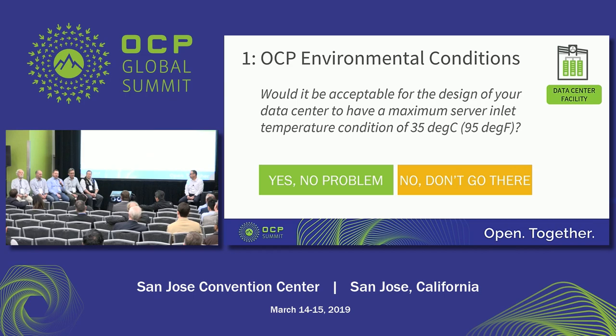I'll skip past the technical bits because I think what's most overlooked is what does that do to your data center technicians? You have people on the floor repairing machines. I have many data centers around the world with technicians who do not like the temperature much above 85 degrees. I don't have a fundamental issue with it from a technology standpoint — I think it's the right thing to do. But I could see supporting it for short periods of time, depending situationally on locations and how long that temperature would be sustained, because at some point technicians need to be able to work in a way that's not detrimental to their health.